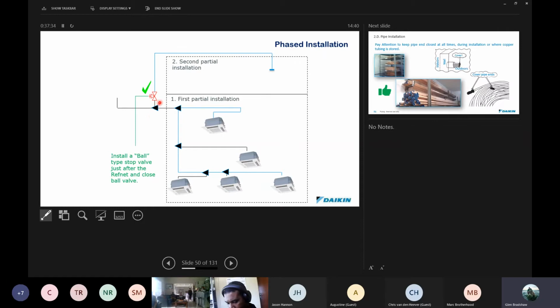What we do recommend in this installation is that a ball type stop valve is installed within 500 millimeters of the ref net joint, and then the piping is continued after that to where the second phase installation is going to start. That valve can then be closed off, so can the piping. You can put a Schrader in here, and at the appropriate time we can evacuate just the section of piping, weigh in the gas charge for the piping, and then we can open up the ball valve. Remember, only ball type valves, these have a low pressure drop. Gate type valves have a high pressure drop, they're not acceptable. So just consider that when doing phased installations.